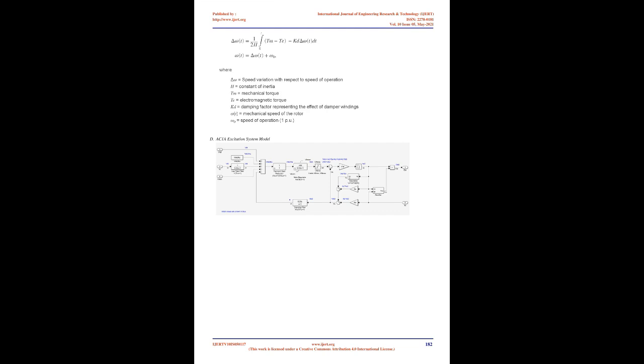To compare the difference between the response of the governor with the controller, in closed loop, and without the controller, in open loop, Figure 4 shows the response of the diesel engine when the governor is in open loop and the microgrid is grid connected. Although the frequency can be maintained at 60 Hz at steady state, there was high oscillation at the initial operation of the diesel engine and it always operated at its maximum capability. Figure 5 shows the response of the system during islanding mode; at the moment when the microgrid was disconnected at t equals 25 seconds, the frequency becomes unstable. On the other hand, small and gradual disturbances will not impact frequency stability, for example a gradual battery drain out.